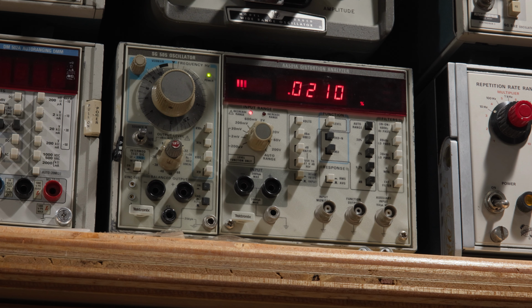So his unit was measuring THD. My unit was measuring THD plus N. Both units also had a different frequency response. His unit was measuring up to 100 kilohertz. The AA501A can measure 100 kilohertz, but it needs to take in the harmonics. So it actually takes in harmonics and noise up to 300 kilohertz. So our measurement bandwidths were different. Our fundamental measurements were different. So we really couldn't make a comparison of data at that point because we were generating fundamentally different data.